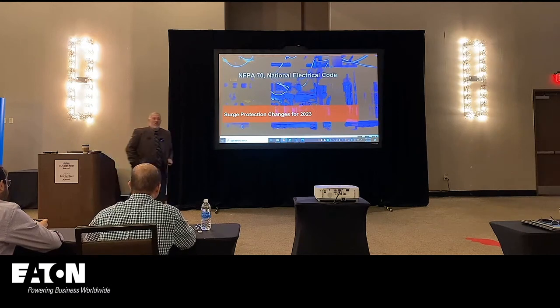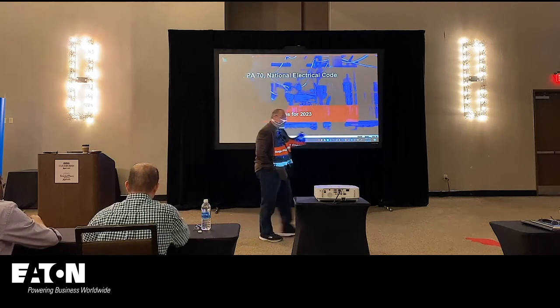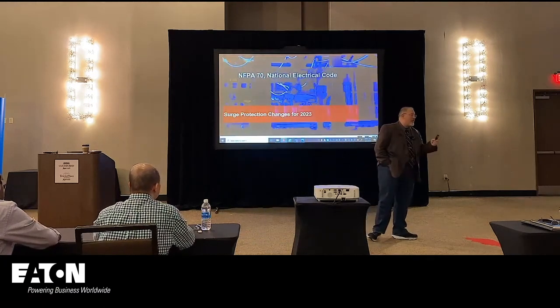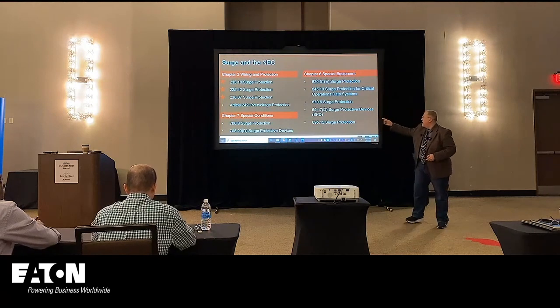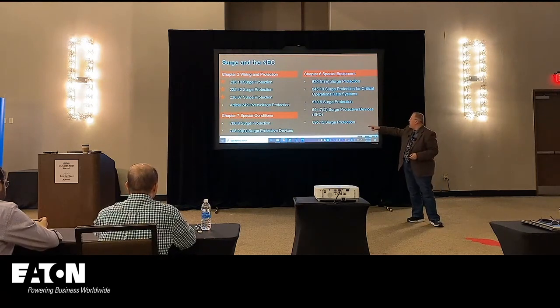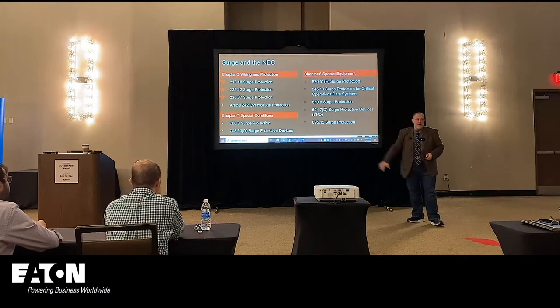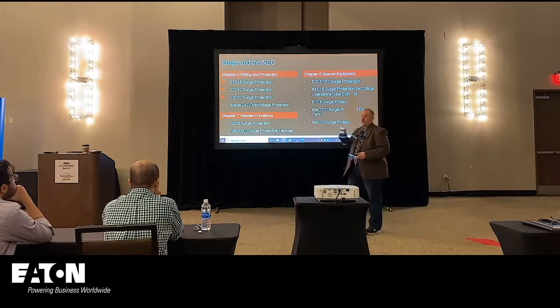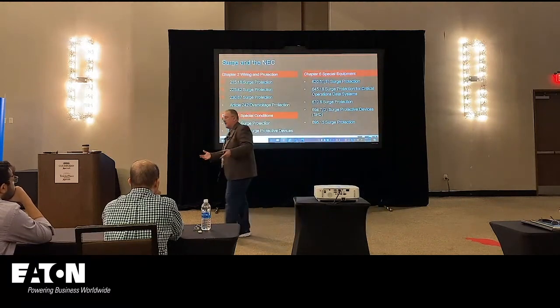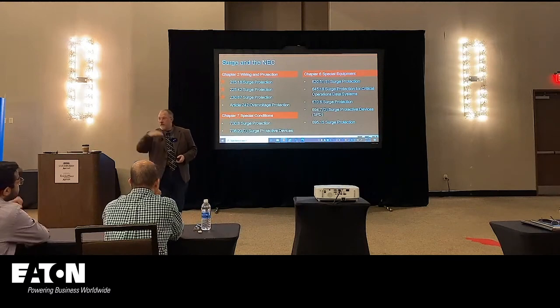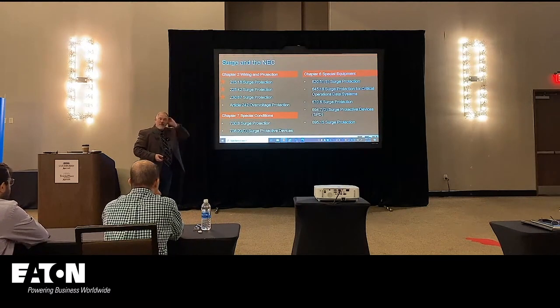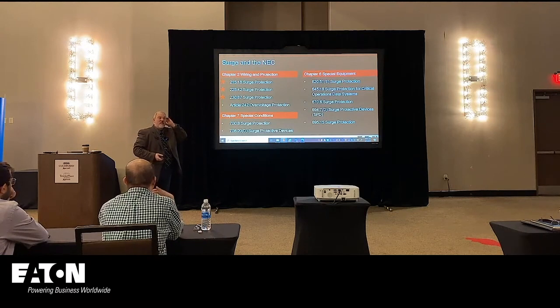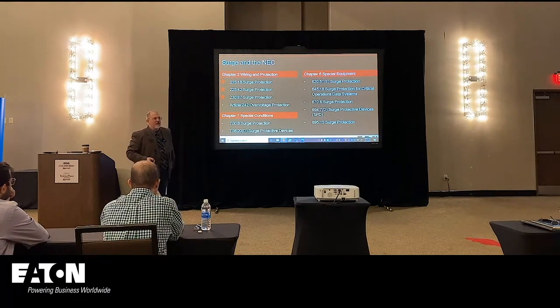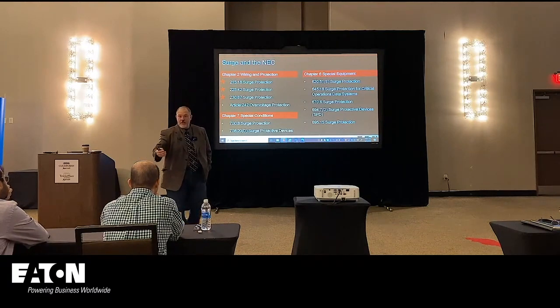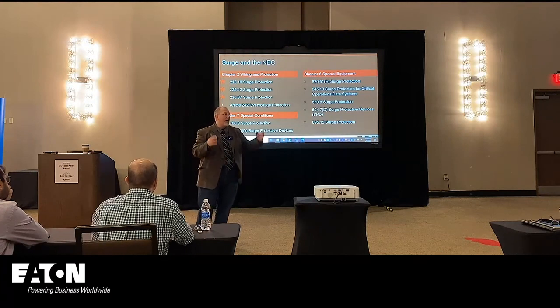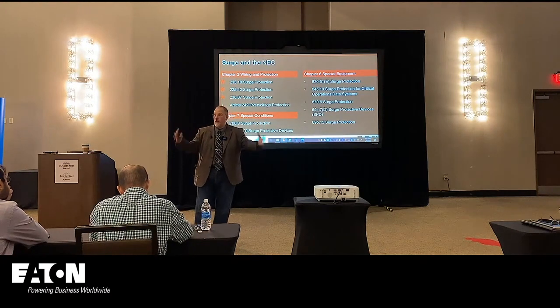All right, surge. We all love surge. Power quality is important, right? So last cycle, what did we do with surge? We put a mandate. So surge has seen a lot of changes over the years. We had requirements in Article 700 and 708 around special conditions for surge protection. In Article 700, any panelboard or switchboard in a life safety system, an emergency system, has to have surge installed. In Article 708, I think that's the first place it was put in, because I was trying to find a justification, and I couldn't find substantiation for the public input for surge in Article 708 systems, because it was put in when Article 708 was created itself.